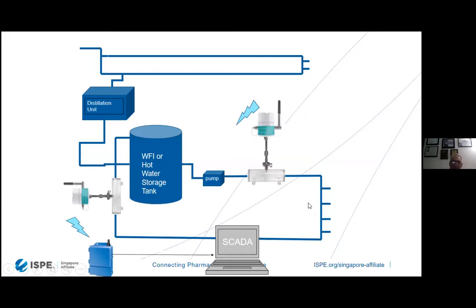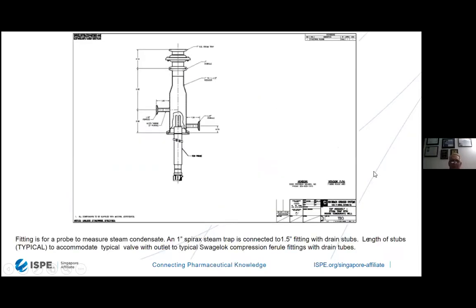You want to see what else is happening in the whole system, you put one on the return tank, return line back over the WFI storage tank, much like what you do with a TOC analyzer and a conductivity monitor, by putting it back before it goes back into the tank in order to show if there's any degradation across the whole system. Of course, that information coming off of these units goes down to a gateway, is then connected over to our SCADA system and displayed on our computer, integrated with all of our information that we're receiving off our automated system.